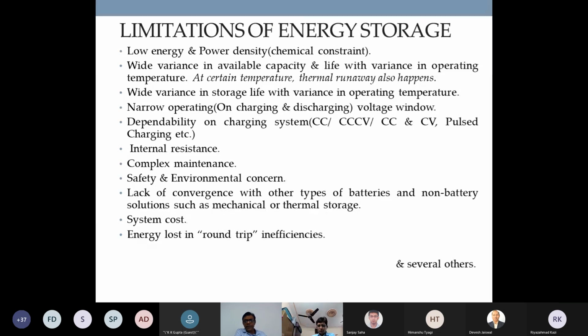Then we are talking about temperature, thermal runaway. Thermal runaway happens with lead acid batteries, it happens with lithium ion batteries, it happens to a certain aspect in nickel cadmium batteries. In VRLA batteries also we have thermal runaway at a certain temperature and above a certain voltage level. So storage life - these are all the limitations.